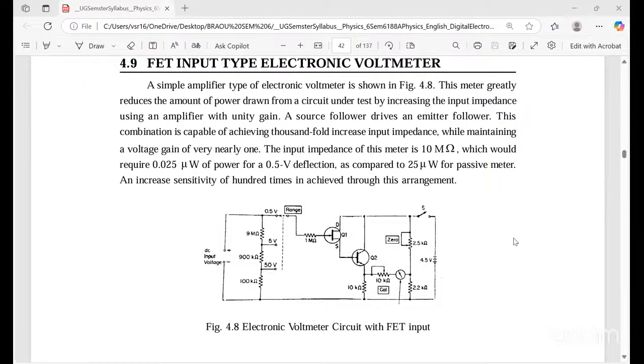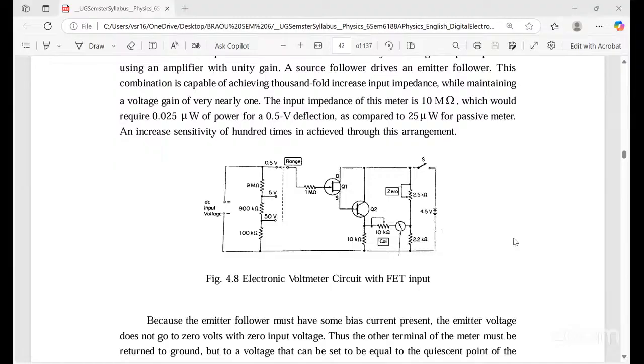The voltage gain is maintained nearly at 1, with an input impedance of 10 mega ohms, requiring 0.025 microwatts of power for a 0.5 voltage deflection, as compared to 25 microwatts for a passive meter. This also increases the sensitivity by 100 times through this arrangement.